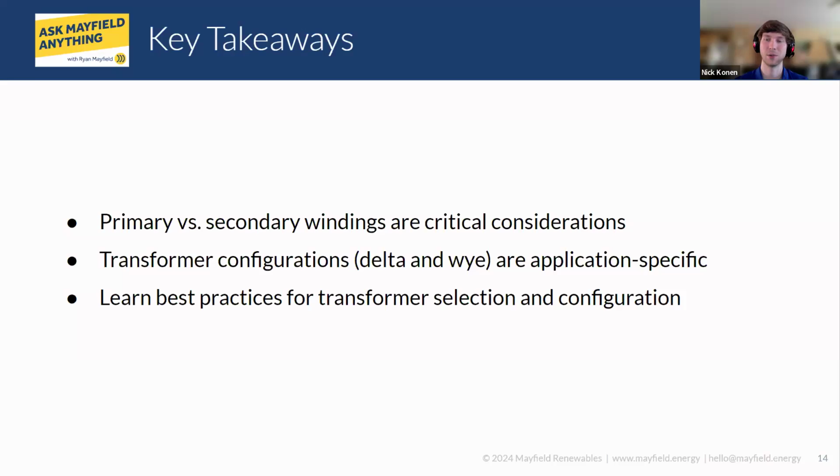Yeah, definitely. The most common is going to be the delta to the Y. There are also YYs in stock as well. A little more limited, but definitely still in stock for many of the standard voltage combinations, running to like a 208 grid or 480 Y inverter, or just strictly 480 to 480 for the isolation there.